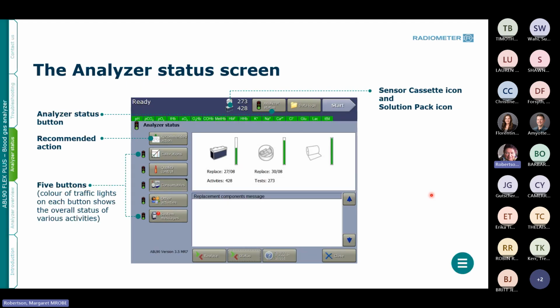All right. Our next screen is the analyzer status. Your button at the top is going to open up this menu. Again, it's going to show you what's left on your sensor cassette and your solution pack. Up here on the left-hand side, you'll see a bunch of other little buttons that are key to what's happening with the analyzer. This will give you recommended actions, calibrations, quality control, consumables, any other services that we may perform, and any system messages. In here, this will tell you when the cassette or the solution pack are ready to expire, it tells you both the tests and the determinations, and it also tells you the date that they need to be replaced. And same thing, it'll give you an indicator on the printer paper as well.